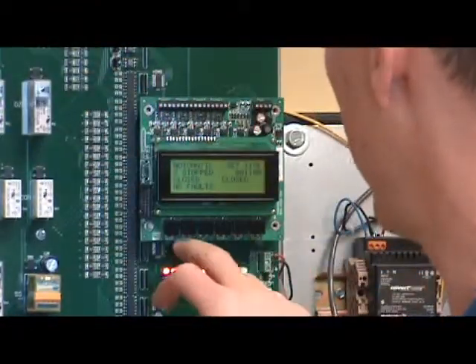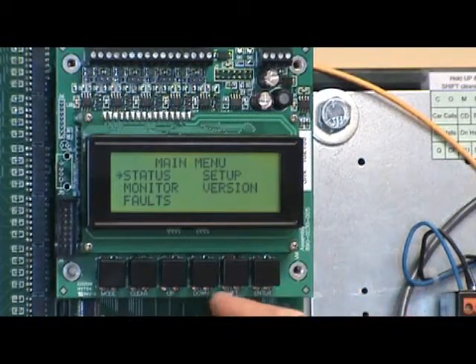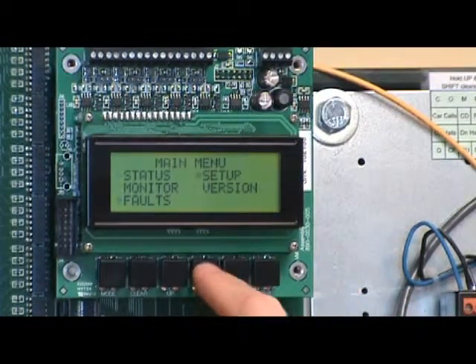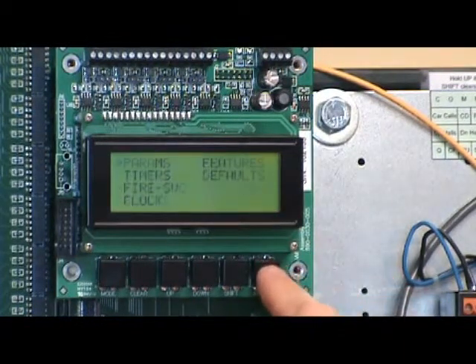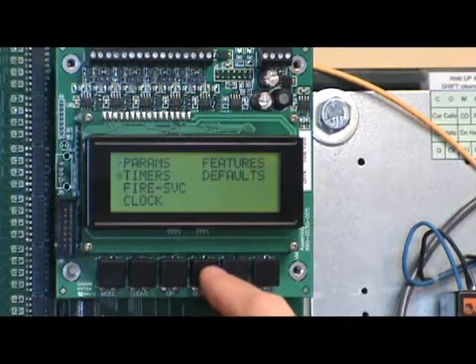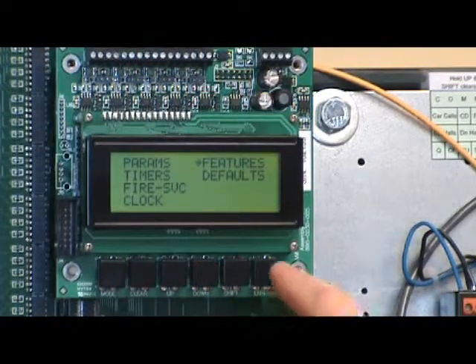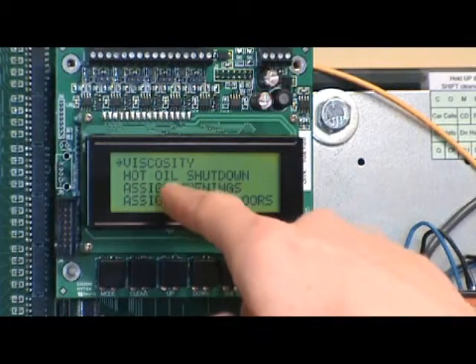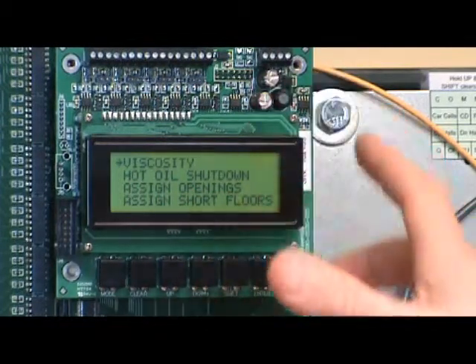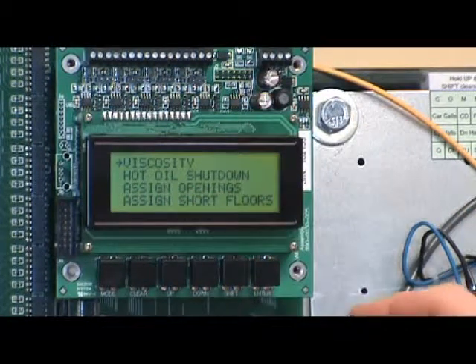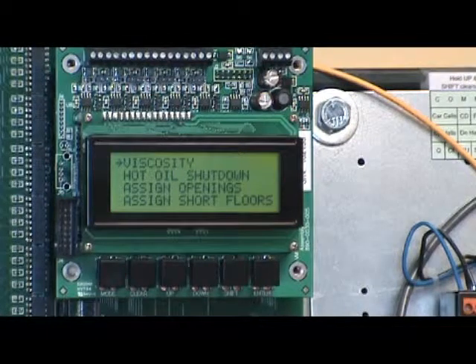Once your sensor is wired up, you're going to need to go in and turn it on. Hit the mode button, and we're going to scroll down, use the down button to setup. You're going to hit enter, and then we're going to scroll down to features. We hit enter. You're going to see viscosity and hot oil are in here as some of the features that are on the controller. They're always on the control system. You just need to order a sensor in order to use them.